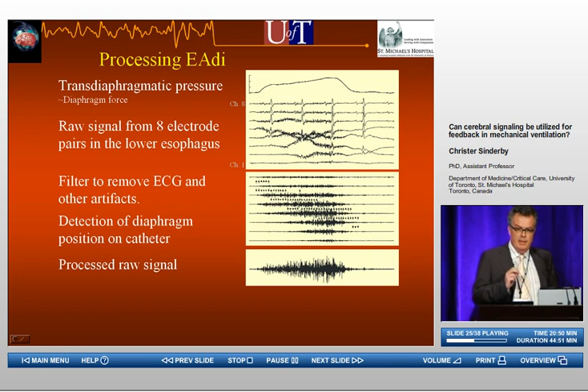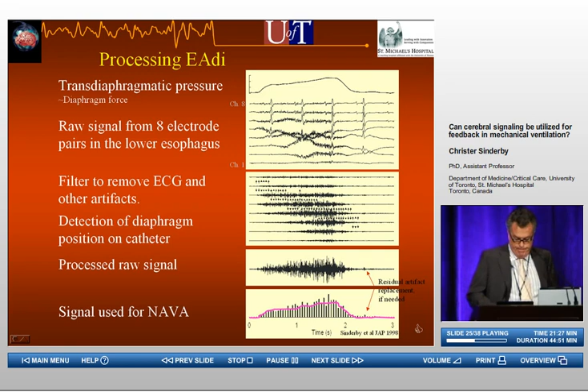Now, if we process this signal further, we get an even more stable signal. You can see we have some small artifacts we can detect and remove here, but here we place the waveform over it, and this is really what we're looking at. This is going from baseline, which means the diaphragm is not doing anything, to the highest activity you can get out of a diaphragm, because this is an inspiratory capacity maneuver. So you can see how you're breathing in, how your effort is increasing, and this is the output you get. This is linked to the ventilator and used to control the assist.